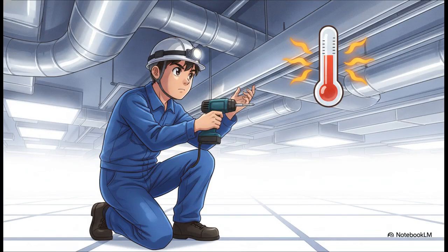The answer? It absolutely must be the totally enclosed type. No ventilated busways are allowed up there because we do not want high-speed air currents blowing dust or combustible particles directly onto live bus bars. Also, keep in mind that false ceilings come with some pretty nasty derating rules. If the temperature up there climbs above 30 degrees Celsius, you have to derate the busway's capacity, and you can never ever run it in an ambient temperature higher than 50 degrees Celsius.